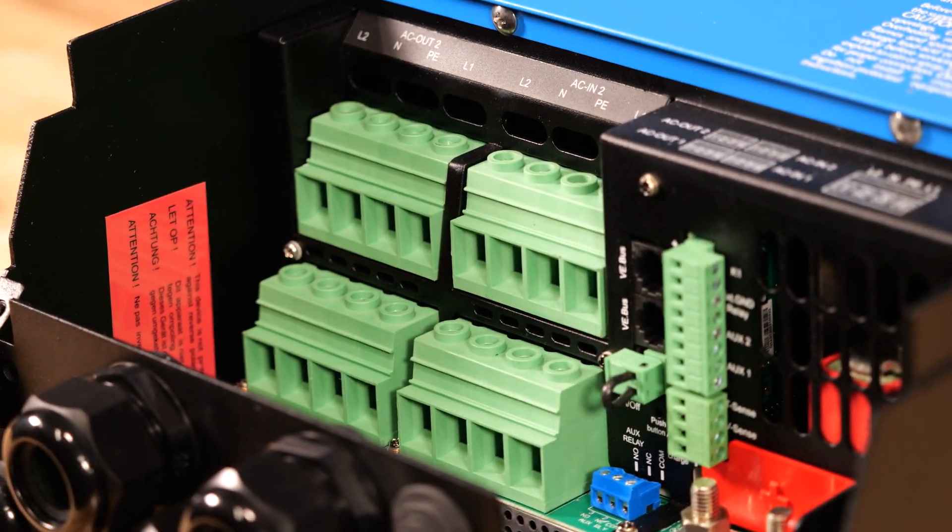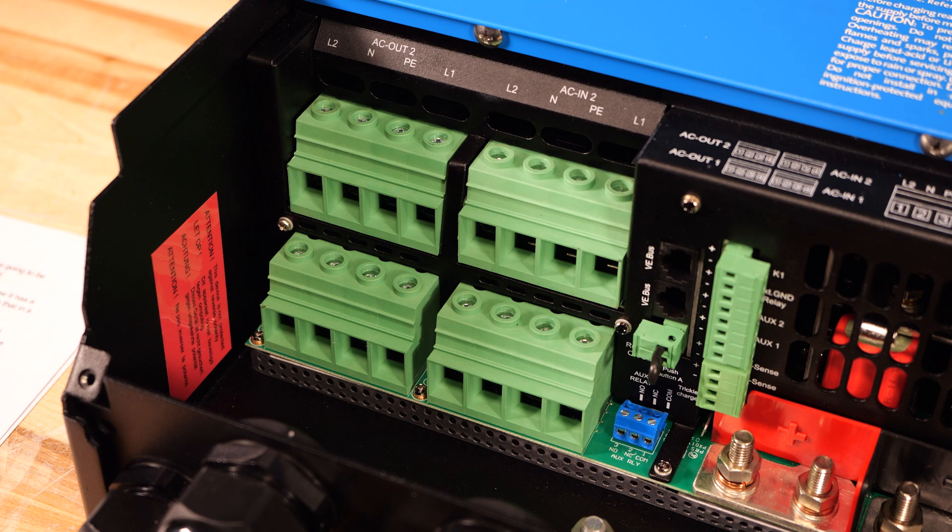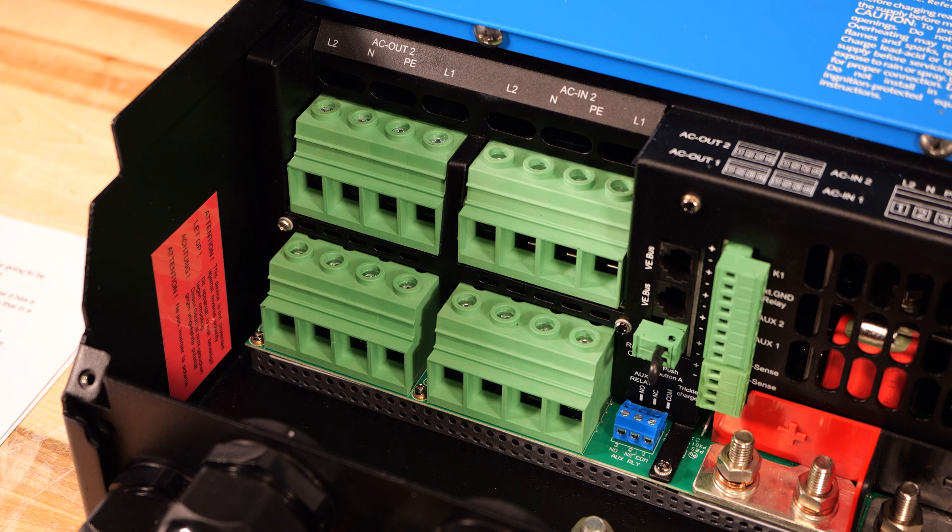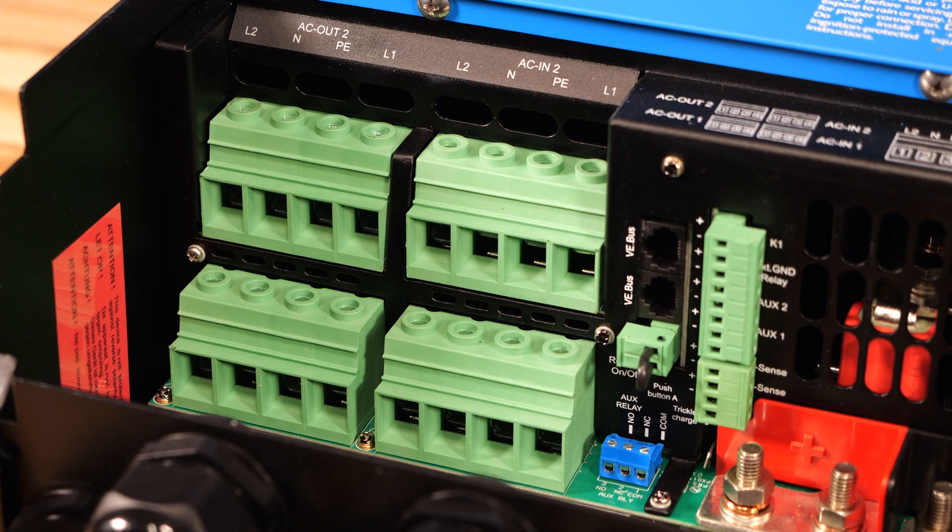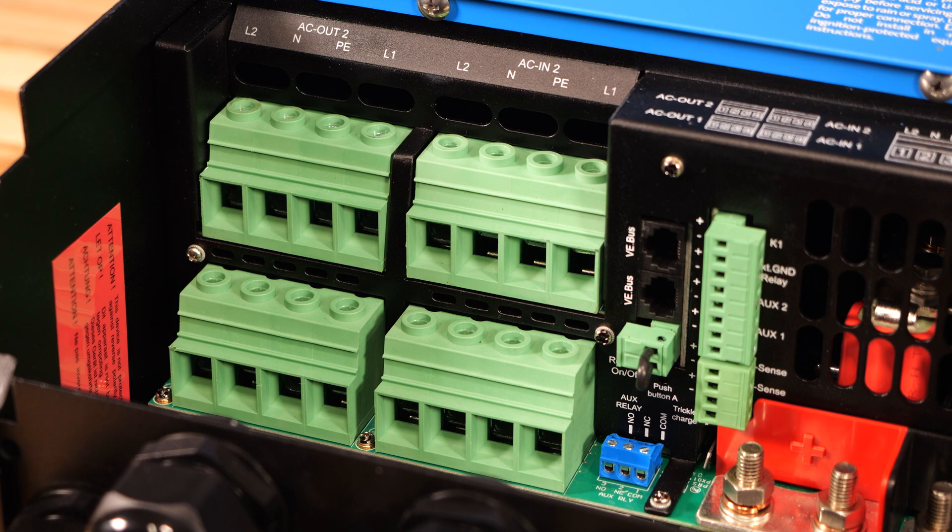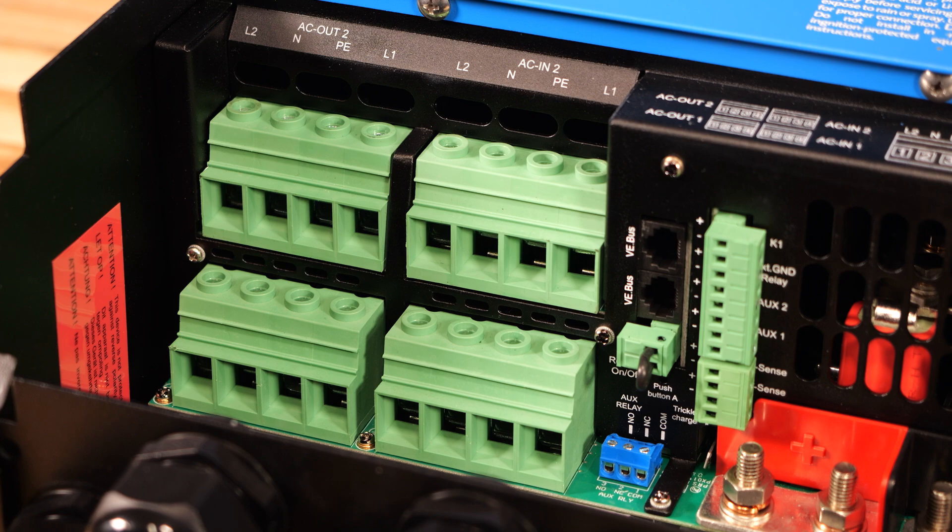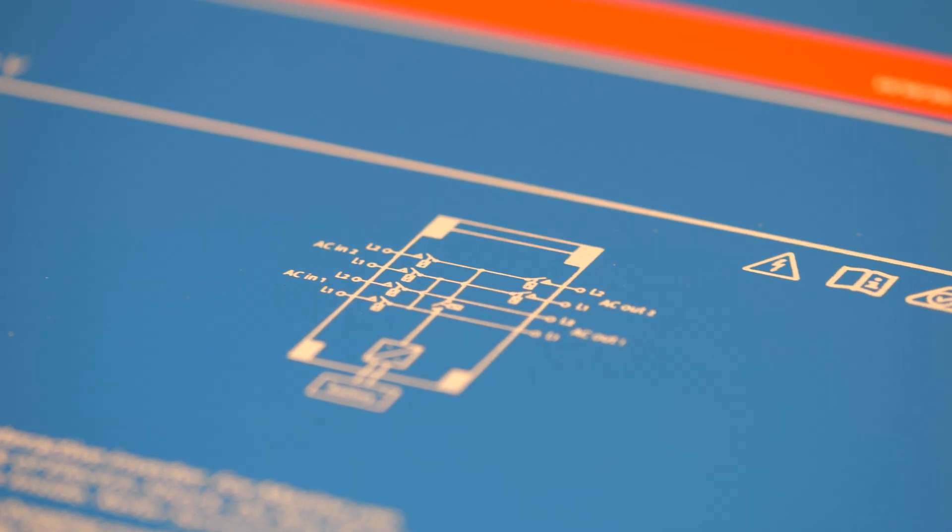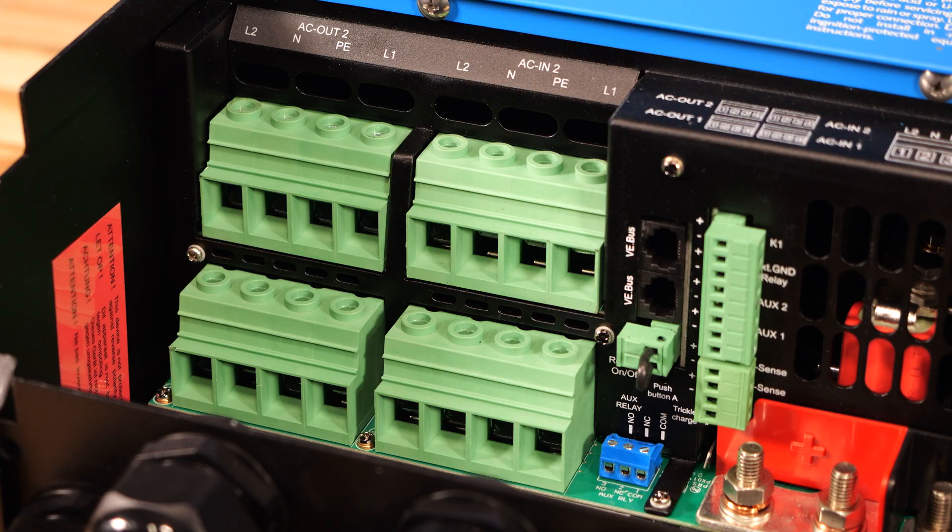You may be wondering why there's so many connections, and that's because the Quattro 2 has two internal transfer switches, so you can seamlessly switch between inverter power, shore power, and generator power. The Quattro 2 is a 120 volt inverter, but because of the transfer switch design, you can supply it with 240 volts to the input, and the transfer switch will pass through 240 volts to the output. With that said, if no input power is available, then an internal relay joins L1 and L2 together to feed the same 120 volt leg to both lines.